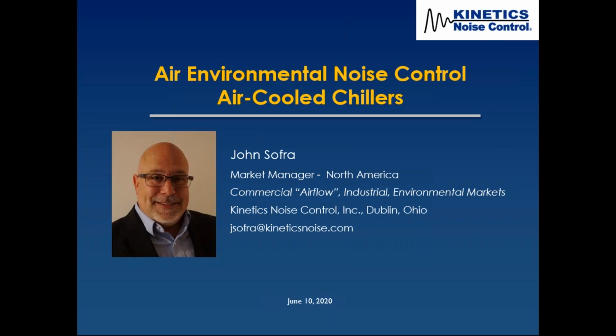If you saw, a few of you participated in a presentation maybe a week or more ago, where Kristen Neath, our Canadian National Sales Manager, presented information on various methods of controlling one of the most common outdoor noise control issues: air-cooled chillers. She presented various ways of solving that noise. What we thought we would do on this next presentation is drill down a little deeper on a specific noise control. We call it our Ultimate Series noise control for an air-cooled chiller. Not always needed, only needed when you need extreme noise control. Probably we see it about 30–35% of the time where this full Ultimate system is needed.